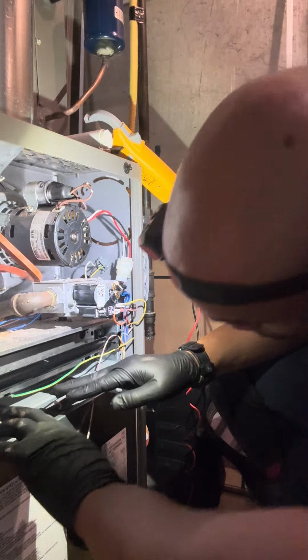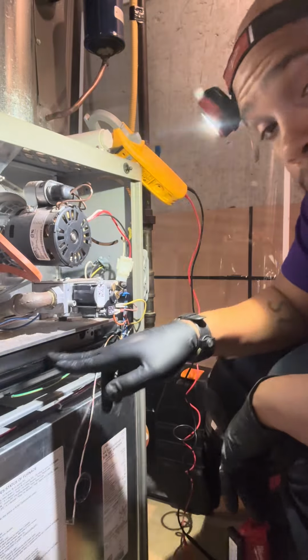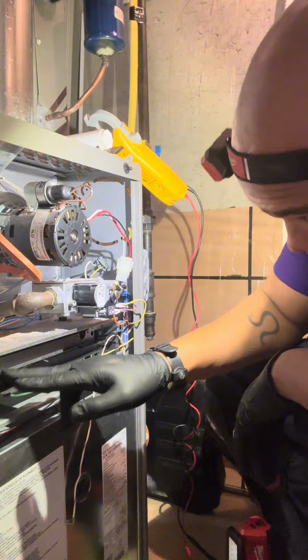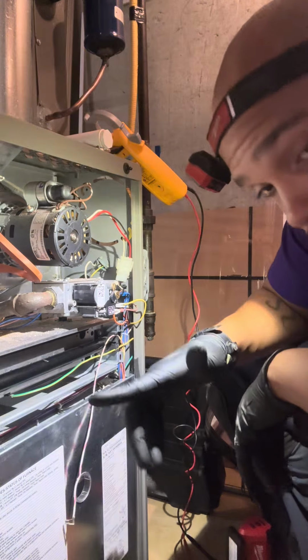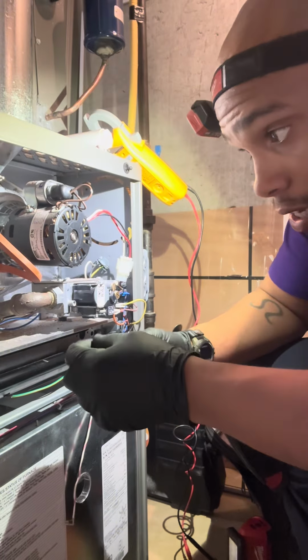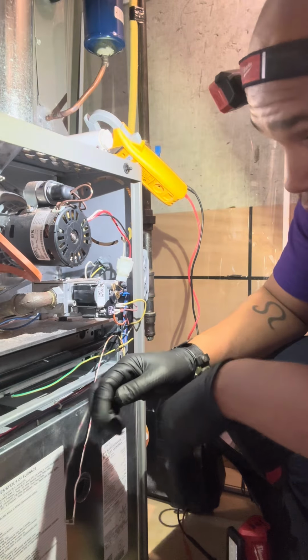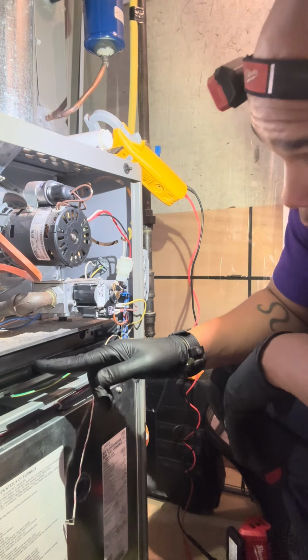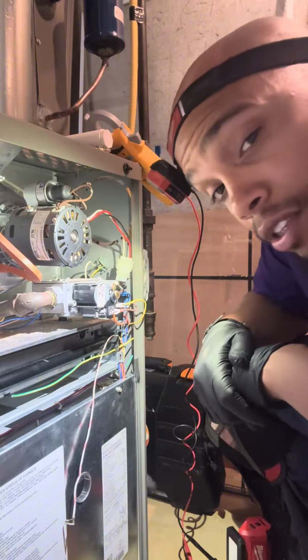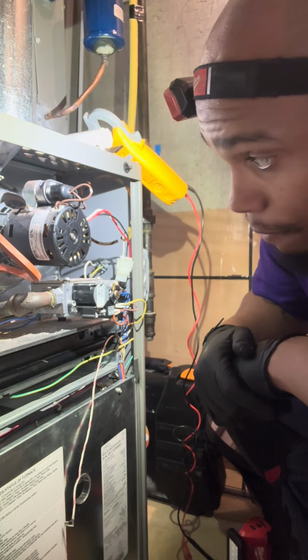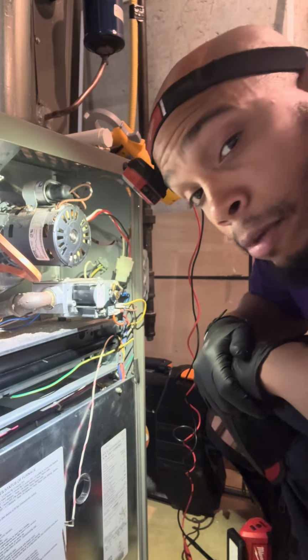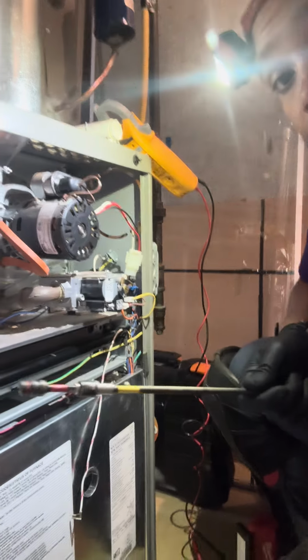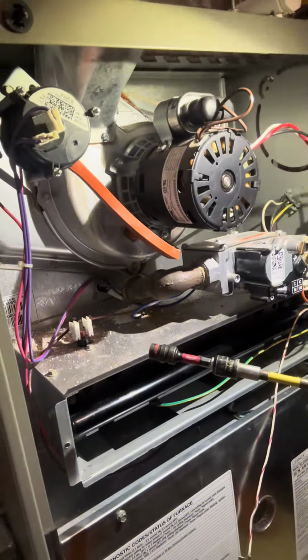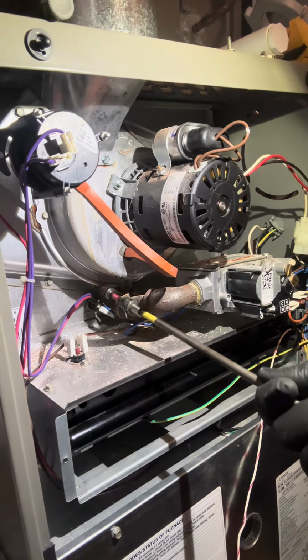And the next thing I'm going to do is get my inspection camera out and inspect these burners. This is a sealed chamber, so it's a little hard to get in and see these 4 burners. You really need a nice microscopic camera. While I have my camera out, I want to have a look at this heat exchanger and see if I can see any wear and tear on the metal. One of the best ways to always get inside and see a heat exchanger is to go in through the high limit switch, which is located right there.